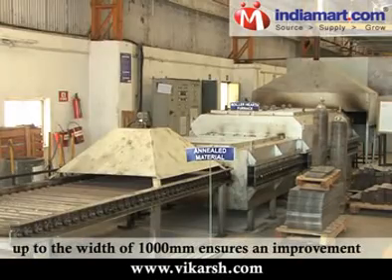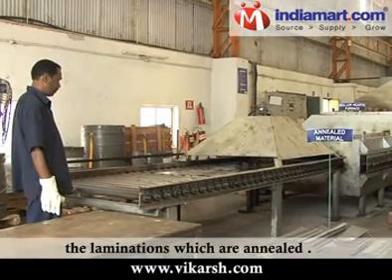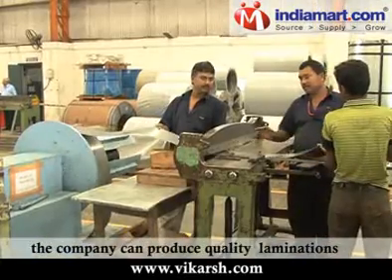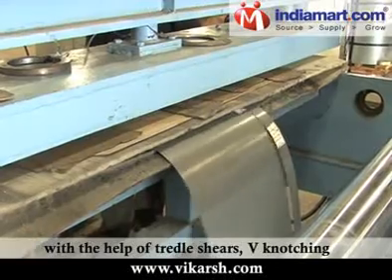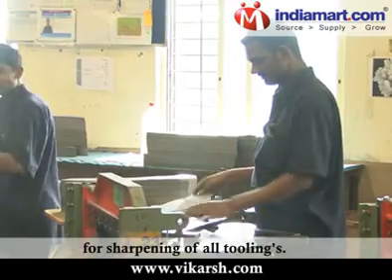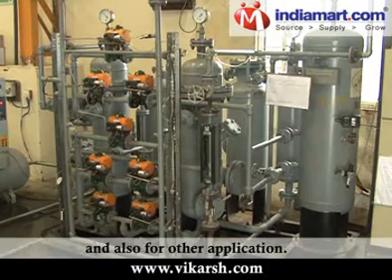A 100 kW 3-zone single sheet annealing furnace up to 1000 mm ensures an improvement of 3–5% on the watt loss of the laminations which are annealed. Besides the CNC method of cutting core lamination, the company can produce quality laminations by the conventional method with the help of treadle shears, V-notching and holing presses, and in-house grinding facilities for shear blades and sharpening of all toolings.